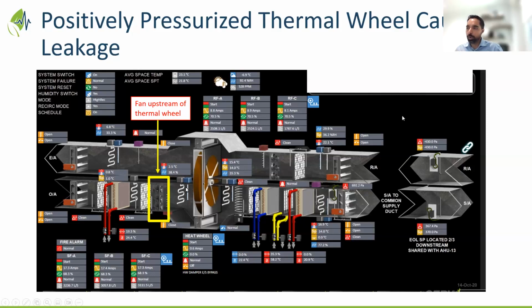So what happens is that the wheel is now seeing almost 7 to 8 inches of static, because that's what the fans are producing to overcome the heating coil, cooling coil, filters, and everything else. There's a huge pressurization, which eventually results in leakage, which is not a bad leakage in the sense that it's a leakage between the supply and exhaust. But the units are underperforming because of that leakage, and in certain cases, in order to satisfy the airflow at the discharge, they have to run the unit harder than what it was originally designed for.